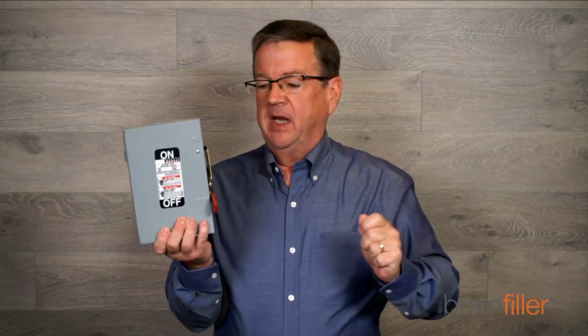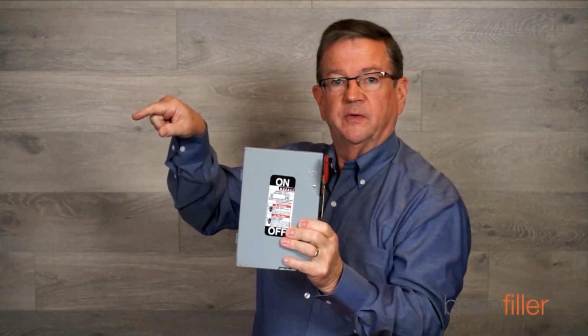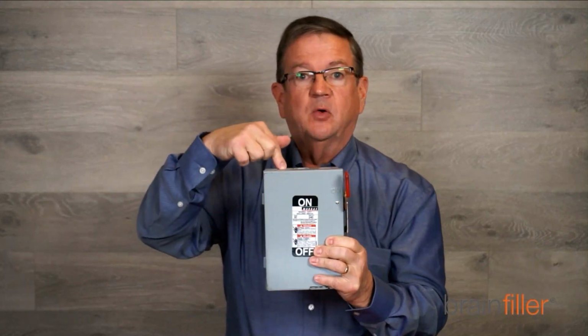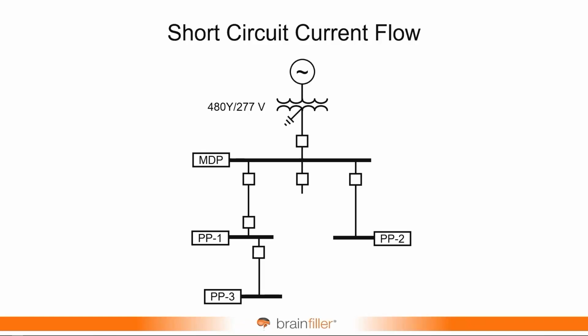You may be thinking, why is that such an important issue? Because picture this. You have your device, you checked all 6 boxes, and you're getting ready to operate it. Well, if the device does not have an adequate interrupting rating, what if you energize it and there's a fault somewhere downstream from here? And the fault current flows through this device, and you're right in front of it, and the equipment's not adequate. What would happen? Well, it could be a catastrophic failure, and you're right there. So this 7th item was added so that when you're checking the boxes, someone has to assure that the device has an adequate interrupting rating. The fault currents vary all over the place, because it's based upon voltages and system impedances and transformer impedances, conductor impedances. It's based on so much data.